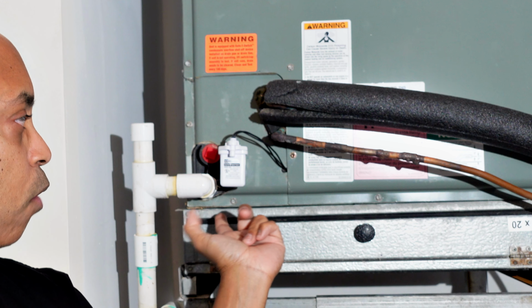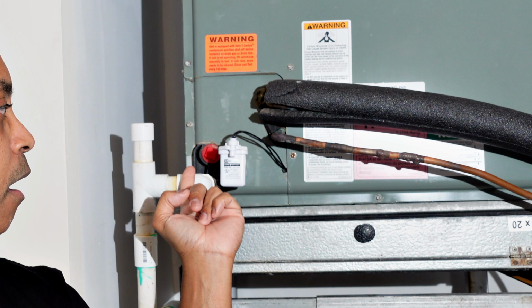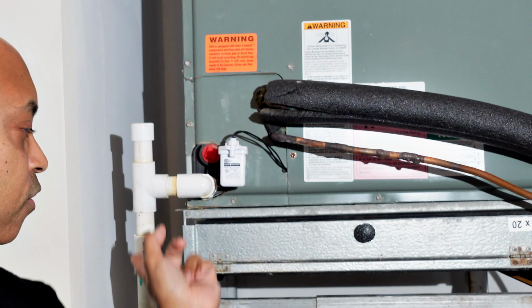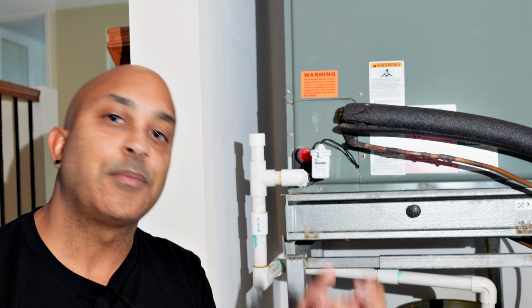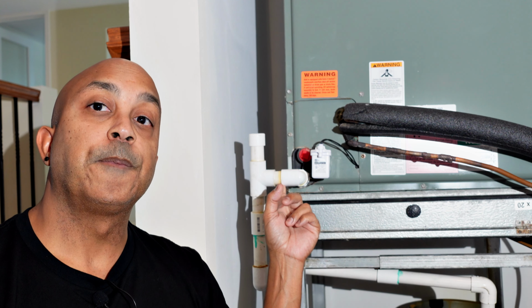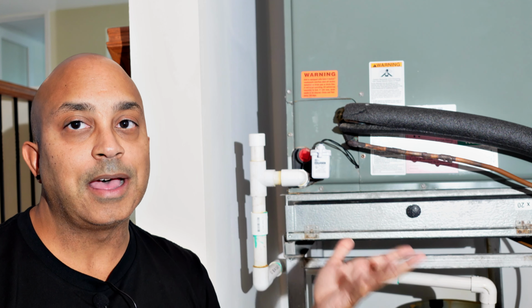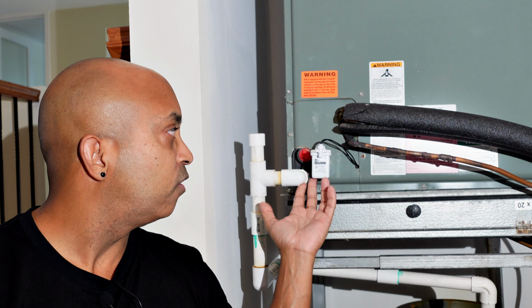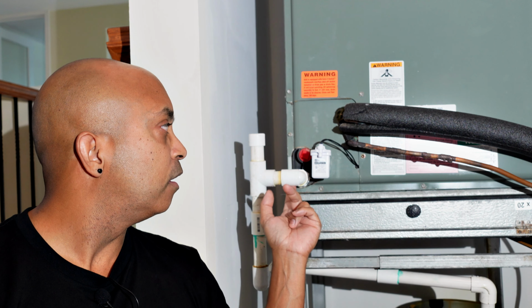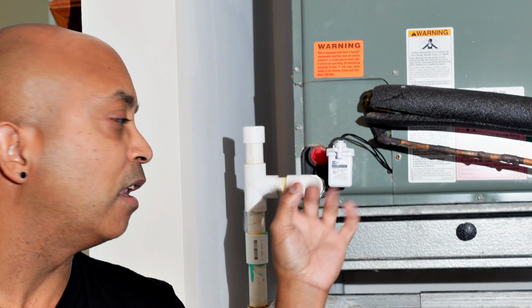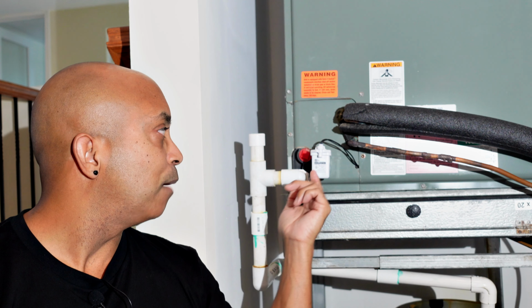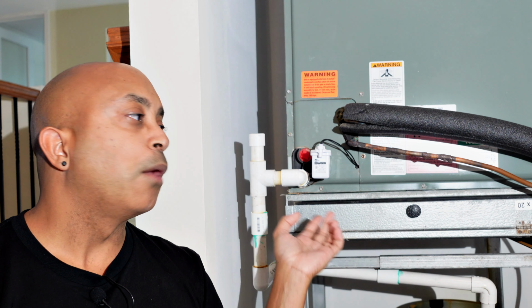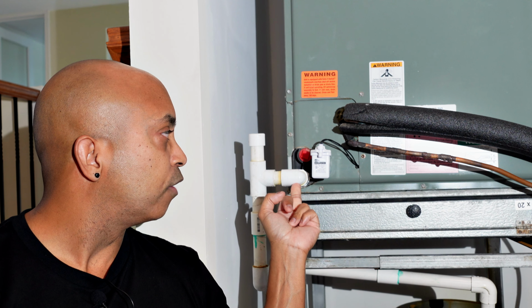What it does is, as the water fills up and accumulates, it flows down this condensate drain and goes down to outside. You'll notice sometimes on the outside of the exterior of your house, there's a little PVC pipe and water is dripping. It's coming from here. Now what happens over time, if you guys don't maintain your AC and change your filter, is algae will build up inside this and it will make the hole smaller and smaller until the water doesn't escape down this condensate fast enough. And what it does is it builds up in the drain pan over time.